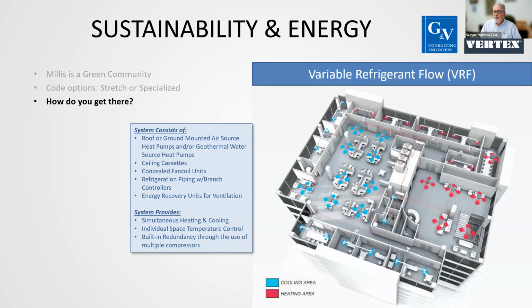One of the things we have to think about too, not discussed in this presentation, is that at the end of this year we're going through a refrigerant change. We're leaving the R410A refrigerant, and industry-wide everybody's moving over to an A2L refrigerant, like R454. It has different characteristics - very low flammability, still non-toxic - but it's causing a change in thinking, and refrigeration codes are being updated regarding the use of that refrigerant. So your schools right now, anything built after 2024 is going to use the new refrigerant.